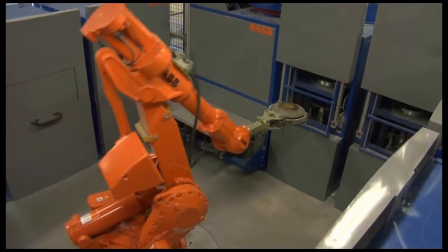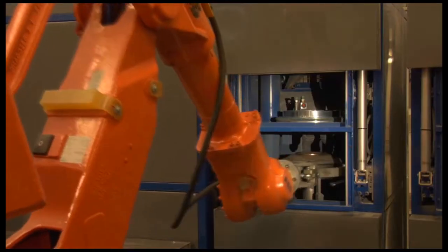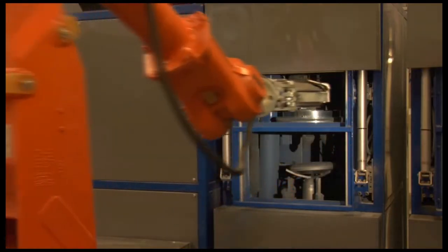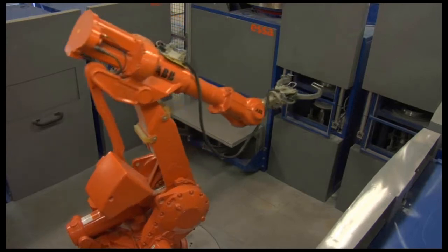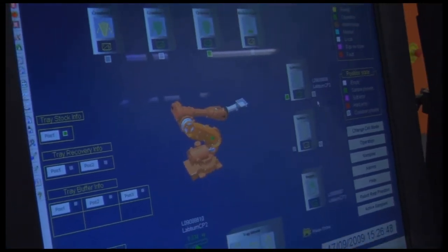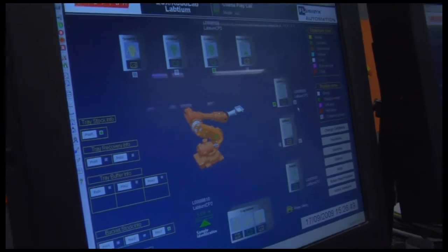In a thorough process, the grinding bowl and puck are individually cleaned with high-pressure glass bead blasting, in order to avoid sample-to-sample contamination. The QCX software tracks the grinding bowl wear for maintenance purposes.